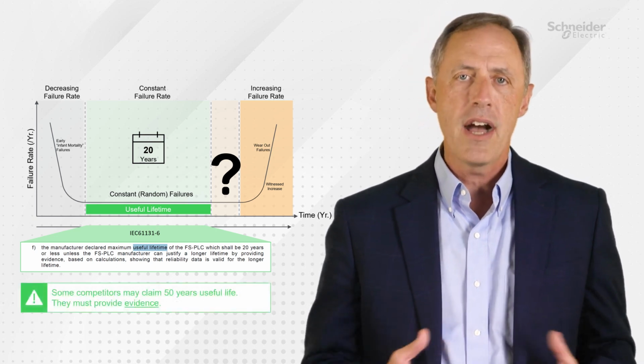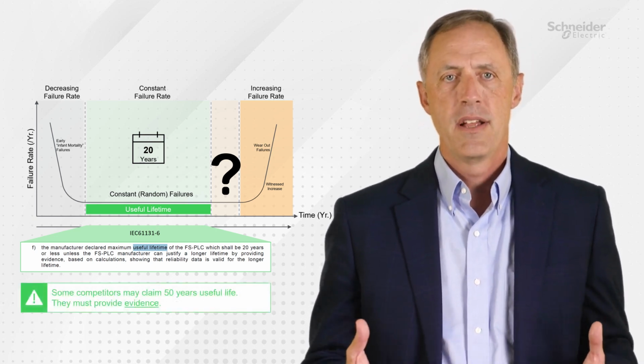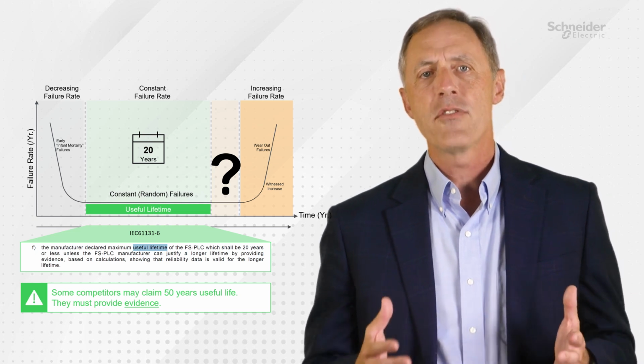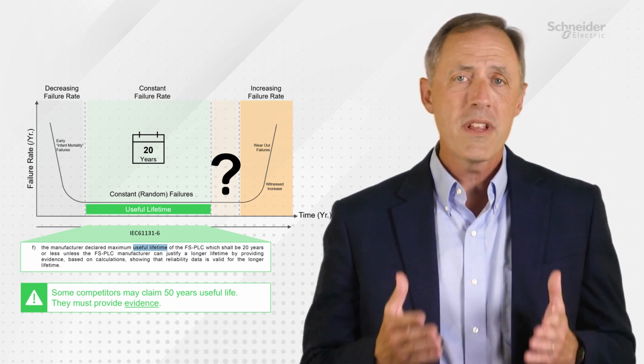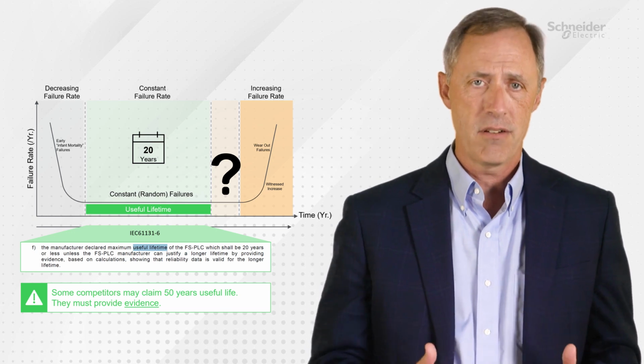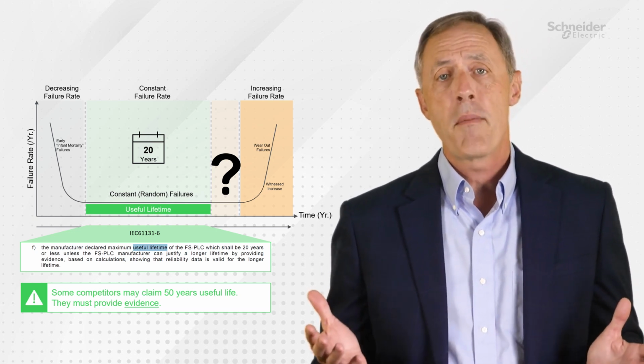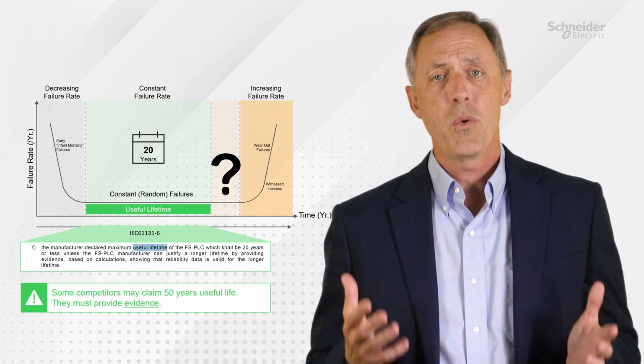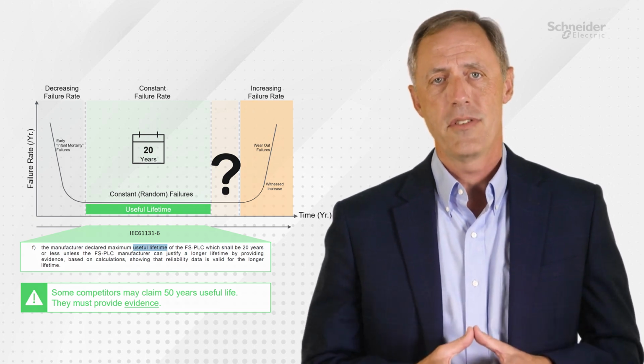Calculating useful life beyond 20 years is nearly impossible, as electronics utilize thousands of individual components of which only the relevant range of failure data is known. And as we remember from our math classes, the accuracy of an equation is only as good as its inputs. Does that mean that safety systems will fail at 20 years? Does it mean that you should replace them at 20 years? Just like in the case of the tires, the answer is no.